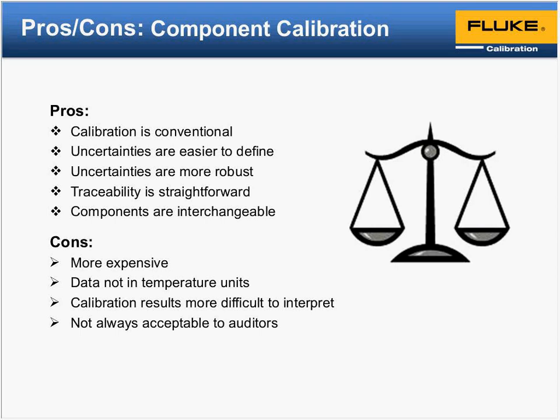Each component, the reference readout and the bath, is going to contribute to the measurement of what we can do. We have baths dedicated to specific ITS-90 temperatures, and we've gone through a very robust process where we include the uncertainty of the reference probe, the uncertainty of the bath, and some other pieces that play in with your U. You crunch those numbers, and that gives the overall uncertainty that we state for our calibration process using a comparison method bath at this temperature. That's how we go about breaking it down.